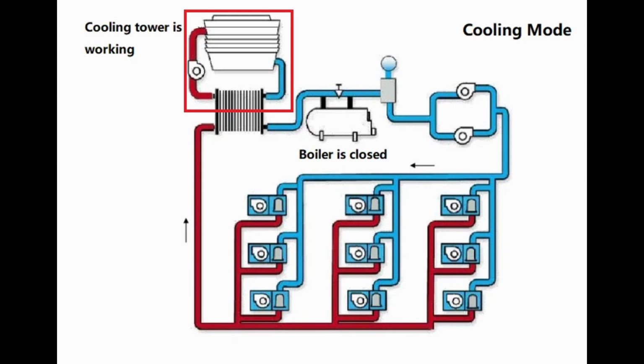Or the cooling tower can be open loop, where the water from the building loop will be sprayed directly over the fill and some of it will evaporate. A closed loop system should never lose any water and will need very little makeup water introduction into the building loop. An open loop system is constantly losing water to evaporation and will need plenty of makeup water to keep the system operational.